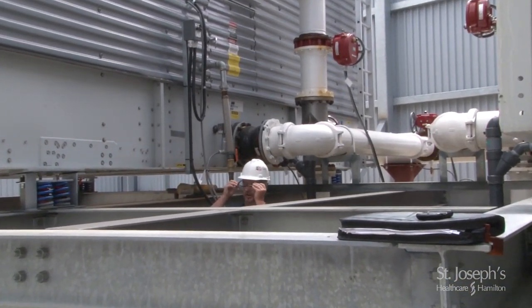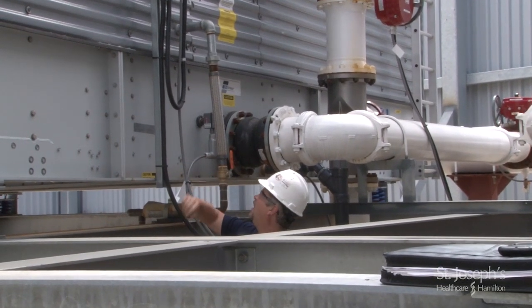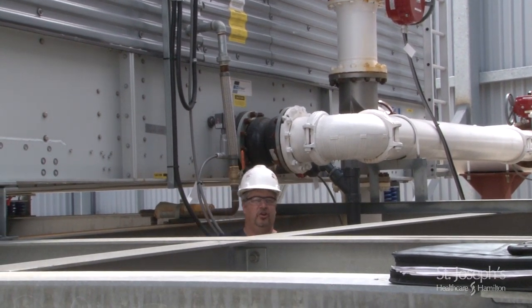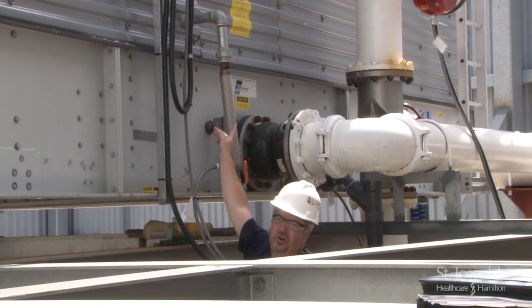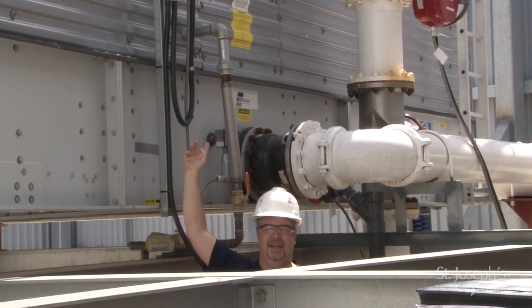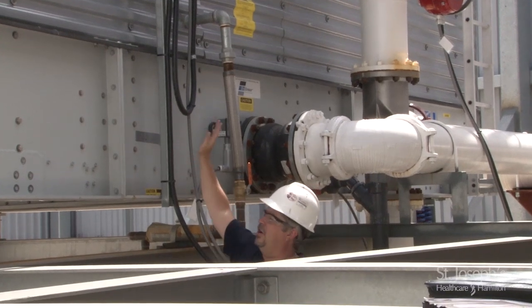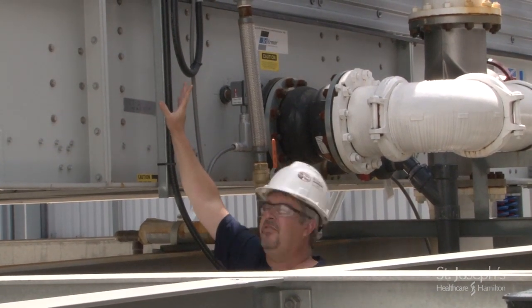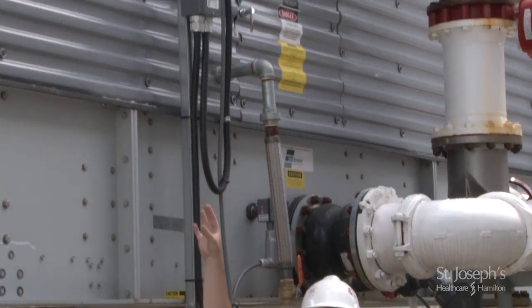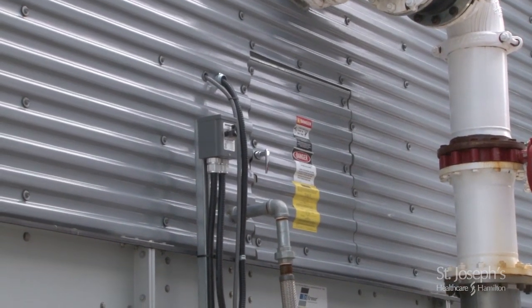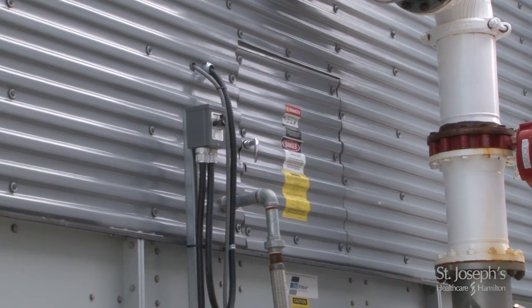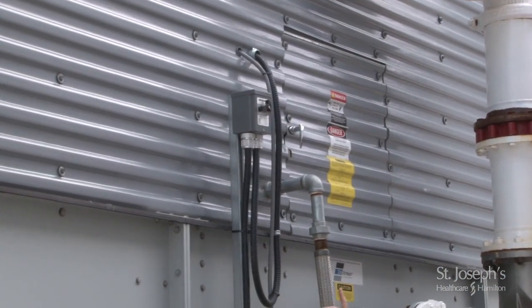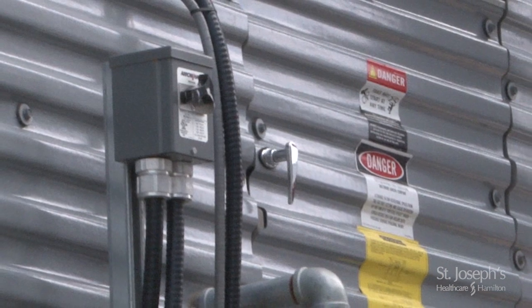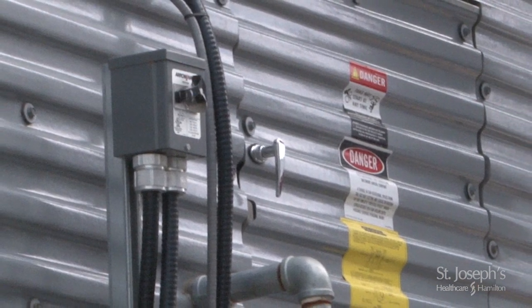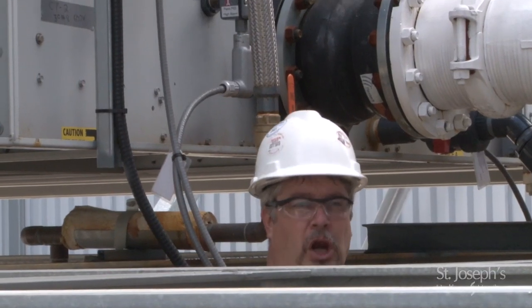Okay, over on this side of the cooling tower, we have some of our connections and our electrical connections, as well as our access door to get into the cooling tower for some of the maintenance. Some of the things you have here is you have your emergency shut-off switch. If something were ever to go wrong with the cooling tower and you need to very quickly kill the power to the fan, you have an emergency shut-off here. Piece of advice on that switch, that's emergency use only. These towers run on variable frequency drives and don't like sudden losses in power.